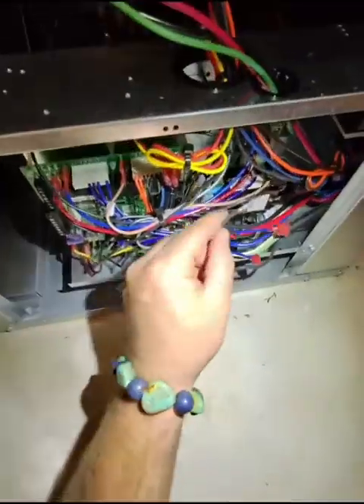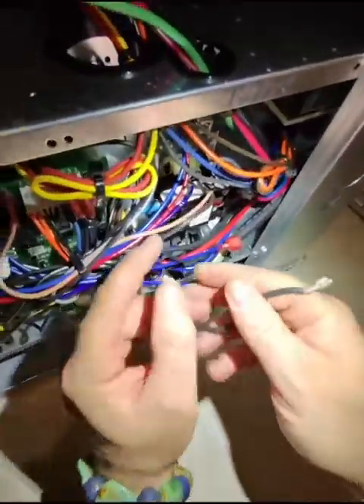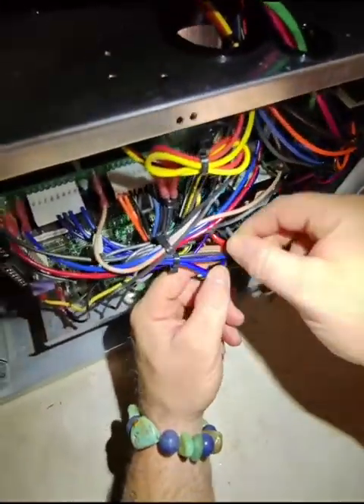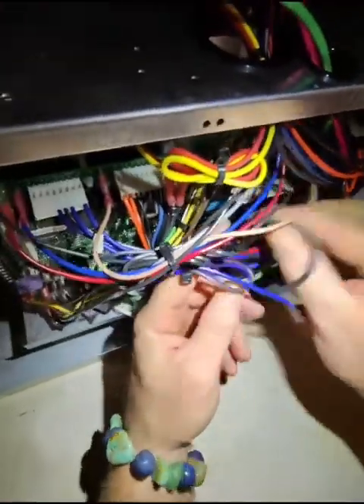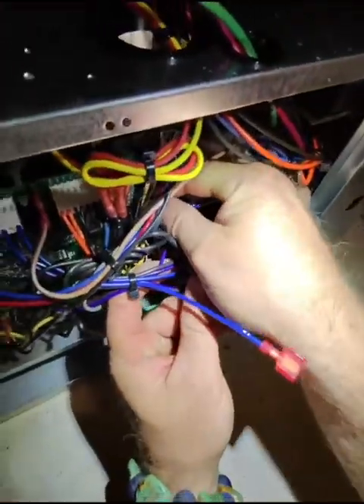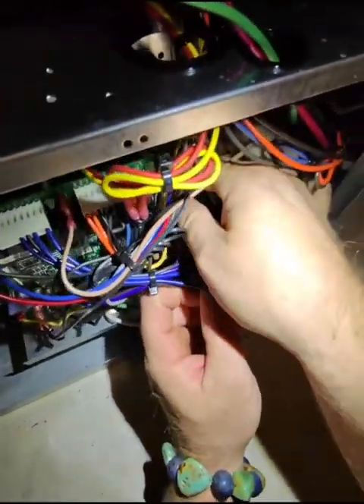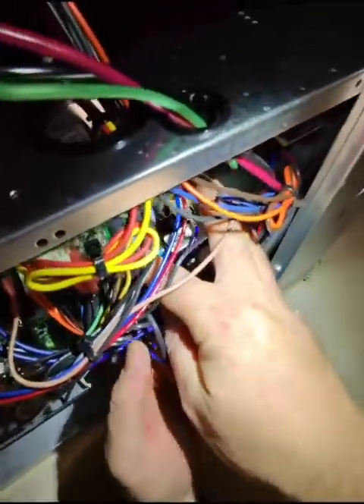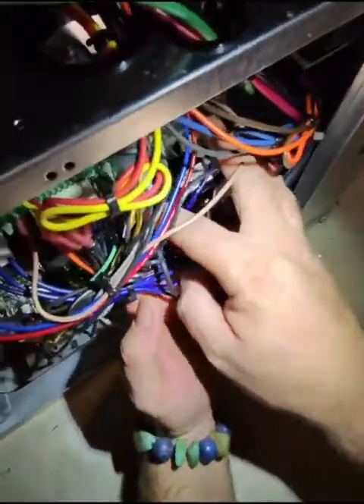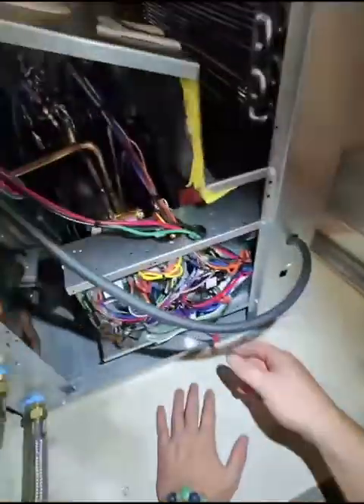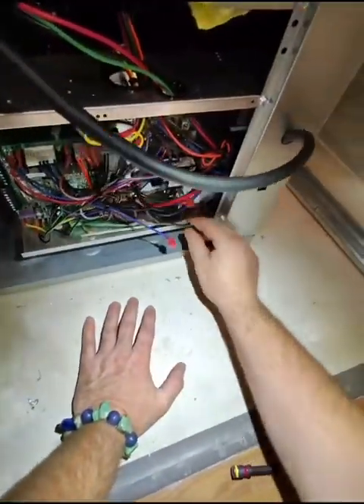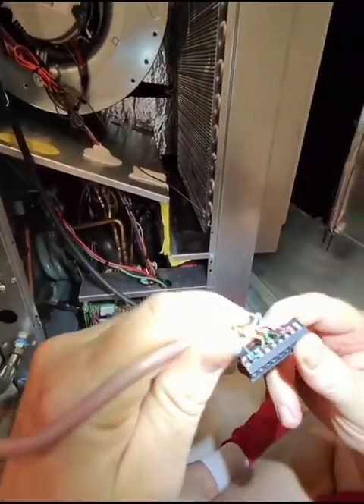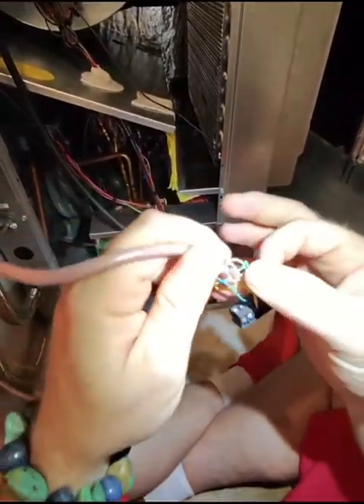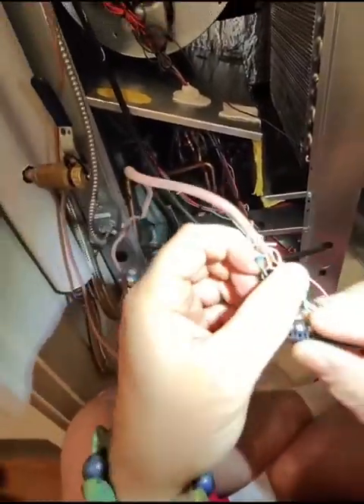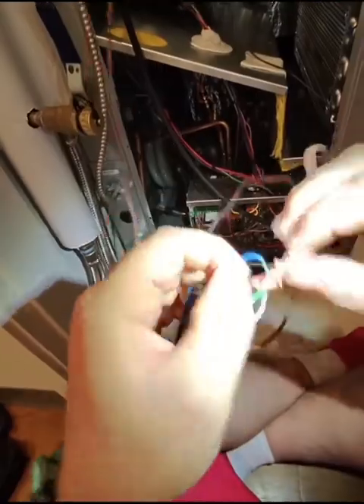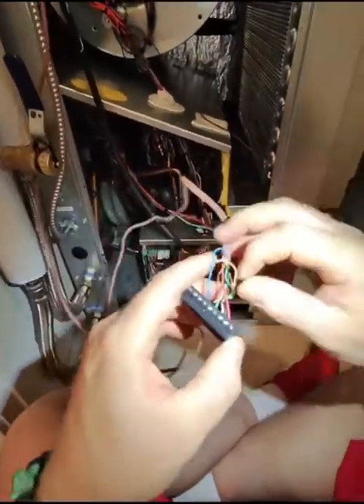Now I gotta figure out where the power goes, and since it's different, you don't want to put the pump's wire on the incoming side of the switch or contact. You got the power coming in, and you put it on the opposite side where the power would come out of the switch, to the pump.